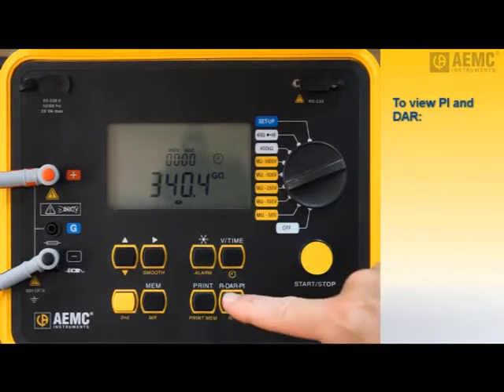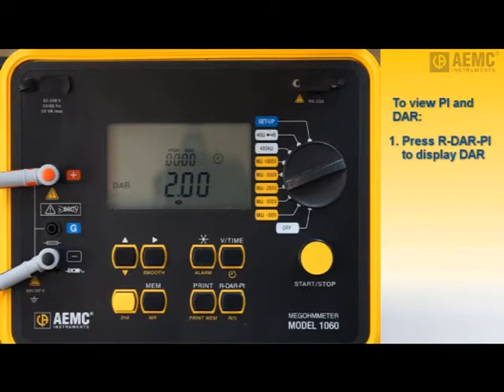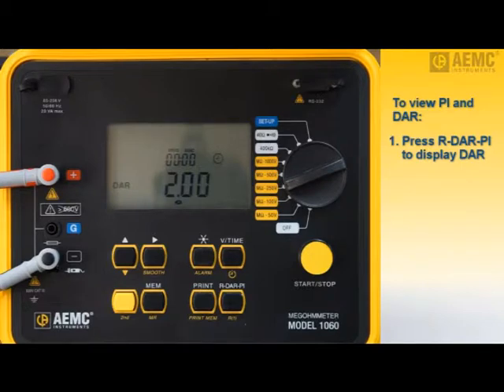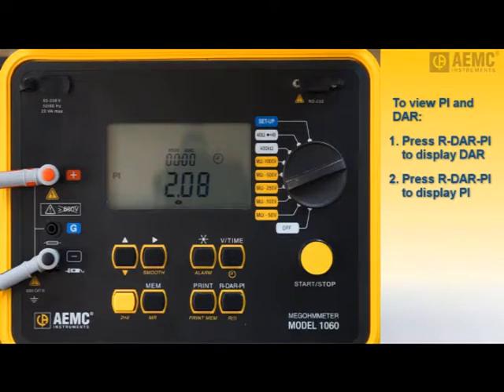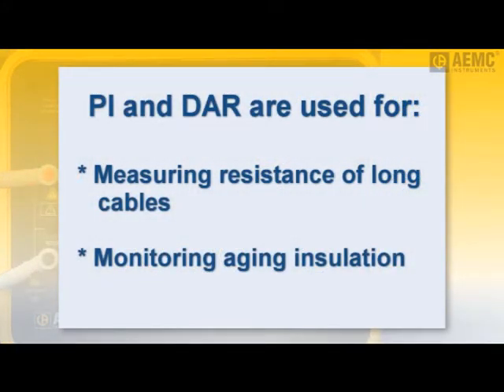To display the dielectric absorption ratio, press R-DAR-PI after the test measurement is complete. This value is derived by dividing the one-minute measurement by the thirty-second measurement. Although DAR is no longer commonly used with newer insulation systems that require longer than one minute of stress before breakdown, it still may have applicability when testing older insulation materials. Press R-DAR-PI again to display the polarization index. The instrument automatically calculates PI by dividing the ten-minute resistance measurement by the one-minute measurement. PI and DAR are useful on long cables or when monitoring the aging of insulation on electrical machines. Measurements of this type can be initially affected by interfering currents from capacitive charges in dielectric absorption; after test voltages have been applied for several minutes, these influences eventually cancel out. So to ensure accuracy, measurements should be performed over an extended period, typically ten minutes or more.